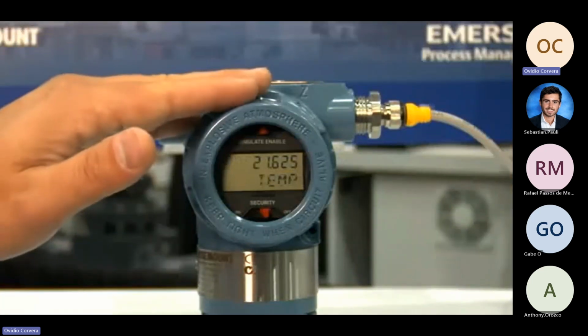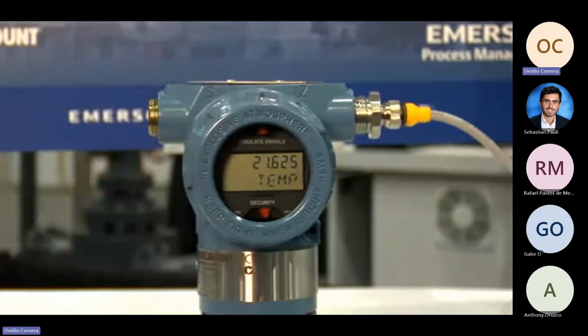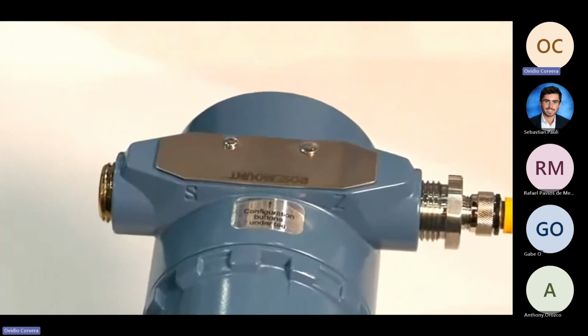The new Rosemount 3051 Profibus pressure transmitter is now Profibus certified to the latest Profile 3.02 standard, ensuring interoperability and backwards compatibility with your Profibus hosts. Beyond Profile 3.02, the new transmitter revision brings to market the first Rosemount Pressure local operator interface, which provides simple and fast commissioning without any additional tools or software. Let's take a look at how it works.